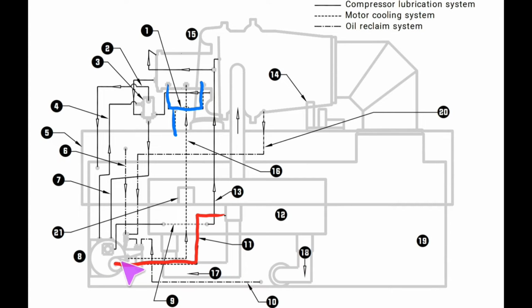So the oil pump runs the refrigerant pump to where it is pulling liquid refrigerant in, and then it pushes it from there up into the compressor housing through this little orifice plate. So this is what assists the motor in maintaining a proper temperature and cool operation, while it's running. And again, all of the additional refrigerant that collects in the bottom, and it all siphons back down into the condenser from here. But this is your motor cooling circuit. This is what your refrigerant pump is doing, and that's what those extra lines that are coming into the oil sump there, if you're ever looking at the face of one, that's what they are. It's all part of the motor cooling side of this system.